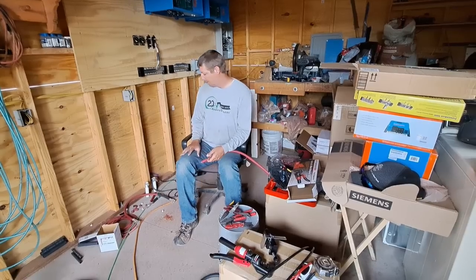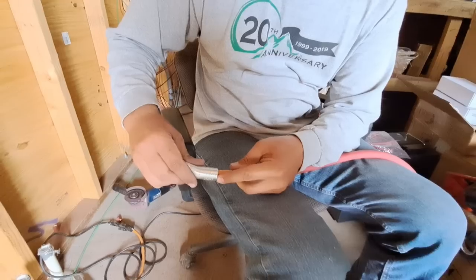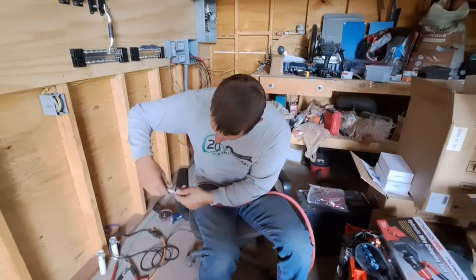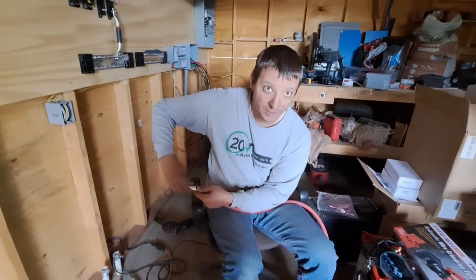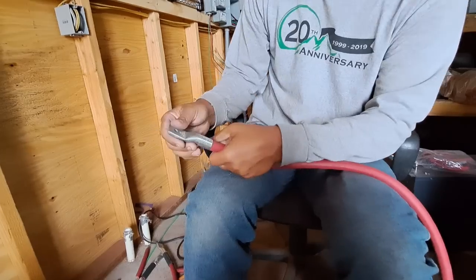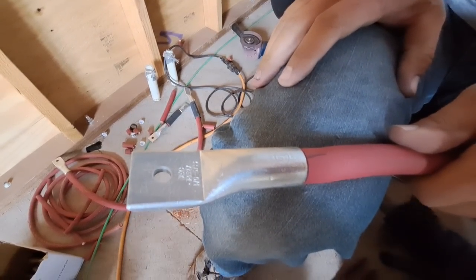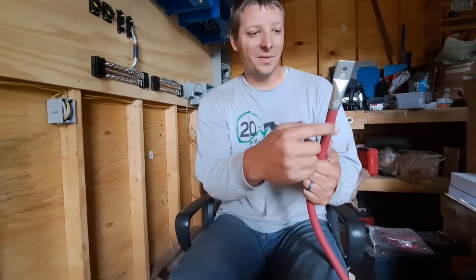How's it coming? Slowly — I've got three cables ready. Welding wire is made to be exposed, whereas THHN is supposed to be in conduit. Oh, I learned something new today! There you go — you're now an apprentice electrician. Look at that — the crimp came right up to where I cut the jacket off, that's how I want them. You shouldn't have any strands sticking out here — that's a hazard.